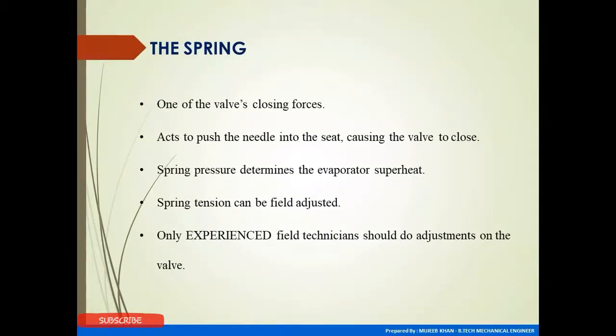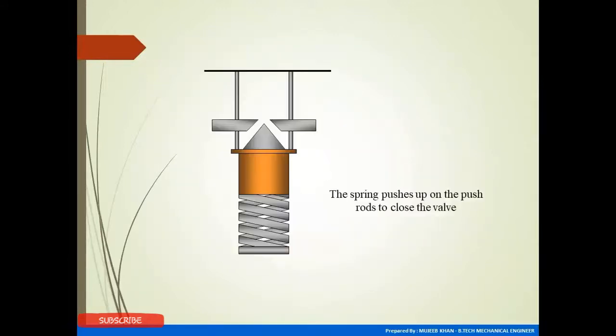One of the valve closing forces acts to push the needle into the seat, causing the valve to close. Spring pressure determines the evaporator superheat. Spring tension can be field-adjusted, but only an experienced field technician should perform this adjustment. The spring pushes up on the rod to close the valve. When the spring moves upward, the valve is closed, stopping refrigerant flow.